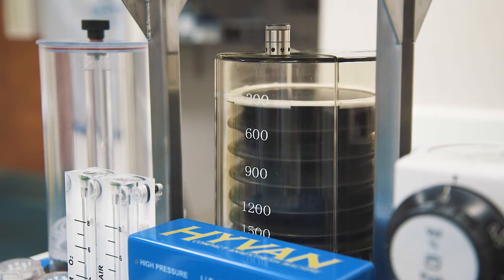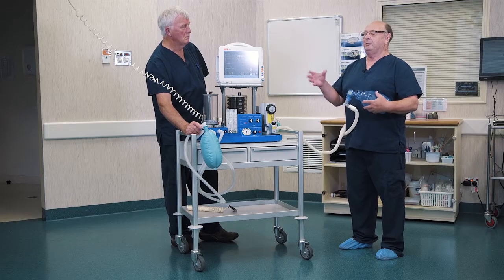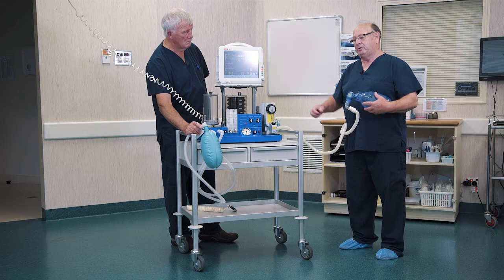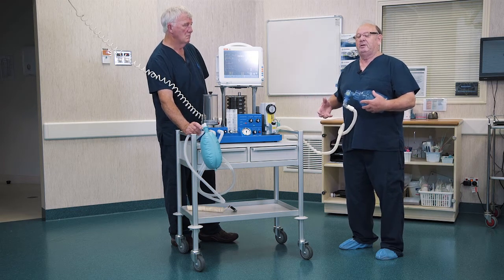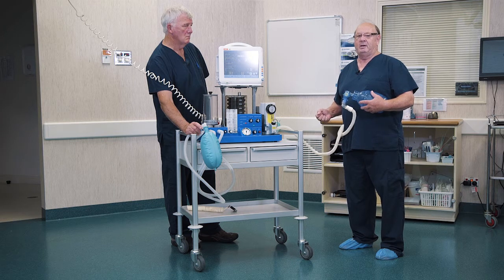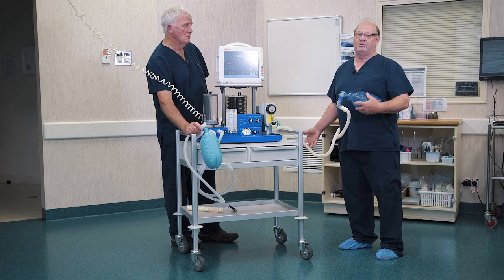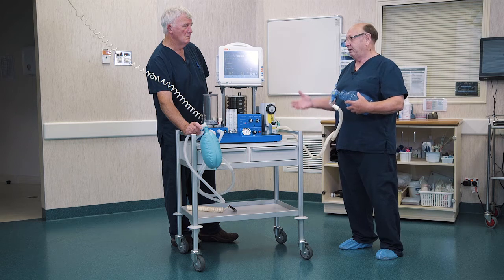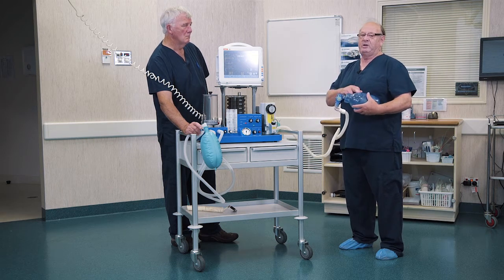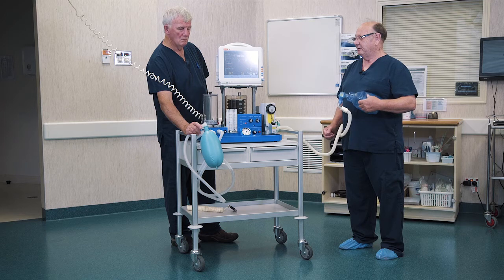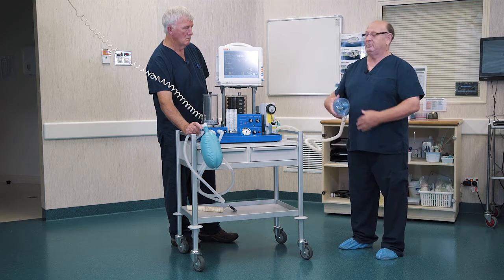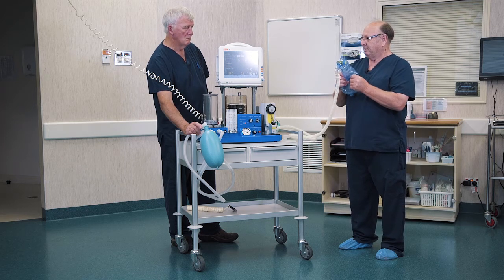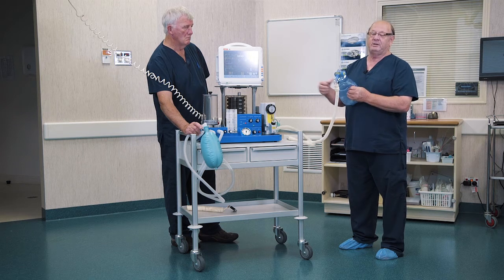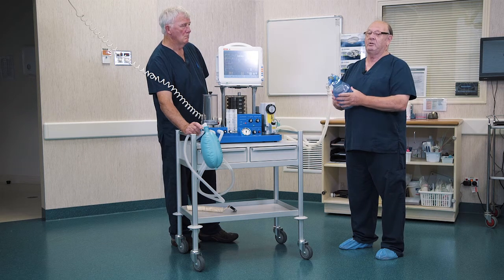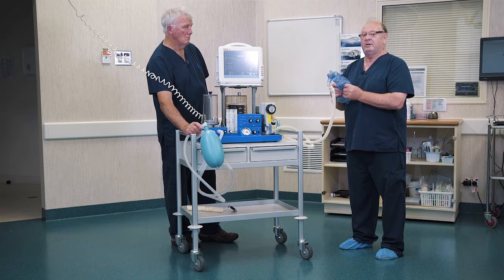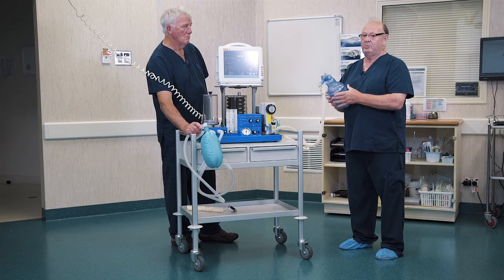If we want to ventilate, normally when you hook the patient to your circuit, you remember you turn the APL valve down and squeeze the bag, and then sometimes you forget to open it. You look around and you have a big weather balloon. Well, that cannot happen with this machine. I squeeze the self-inflating bag like this. I push the bellows up and down. In fact, if I hold this, after a few seconds, it will release itself. There's absolutely no way that you can lock up the system and give the patient a pneumothorax. There's no way you can do that.